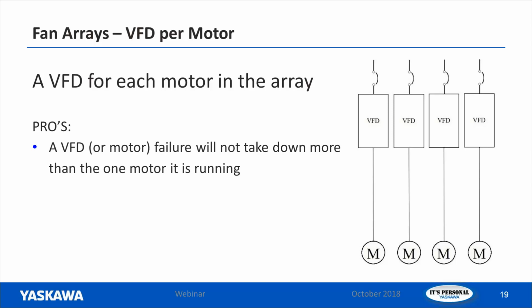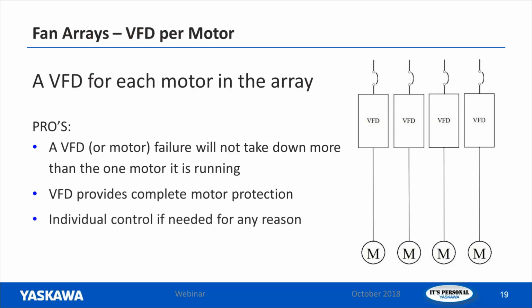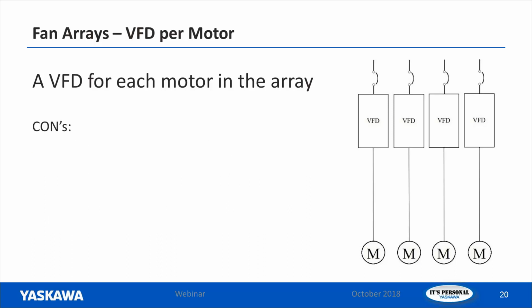So some of the advantages here would be a motor failure is not going to take out the array. You're just going to lose that one motor. Or a VFD failure. Either way, it's just going to take out the one, and you'll be able to run with the remaining motors. But also a VFD provides complete motor protection for a motor. So when you've got one motor on the output of a VFD, that VFD is better than an overload and fuses combined. Next, you do have the ability of individual control of those motors if you needed it for any particular reason.